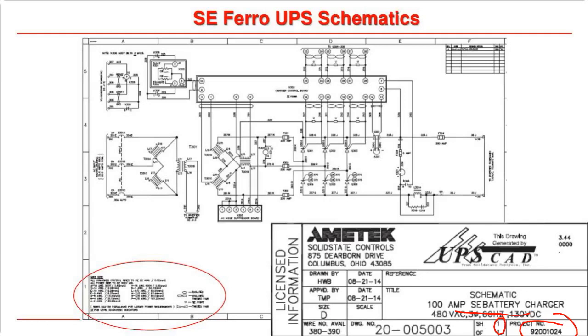Is this the best way to do it? I personally would have liked the charger, inverter, and static switch drawings to be sheet 1 of 3, sheet 2 of 3, and sheet 3 of 3, or something like that. But remember, we do sell battery chargers individually, and we sell inverters individually. So that's why the drawing is labeled as sheet 1 of 1, because there is only one drawing for the charger. And I've circled this in the bottom left-hand corner. This is not always in the bottom left-hand corner, but it is describing what all the cable sizes are.